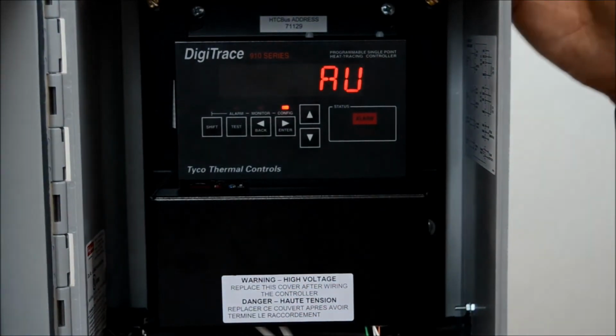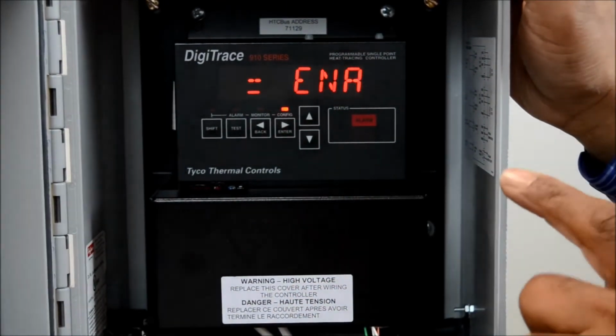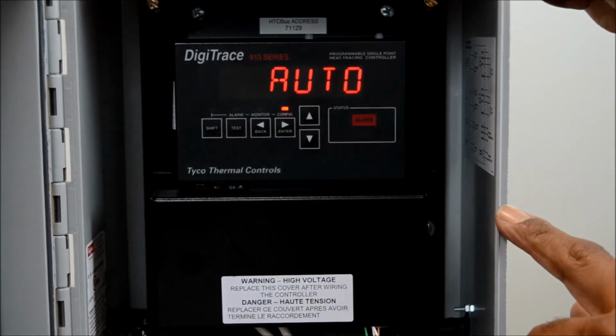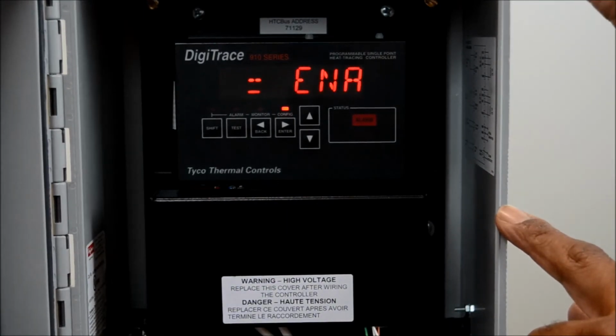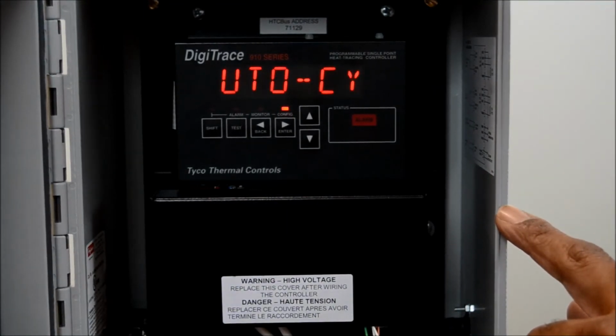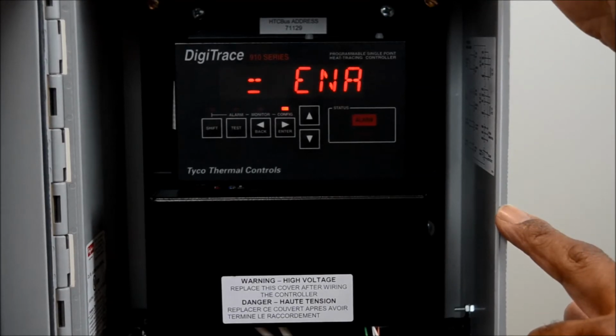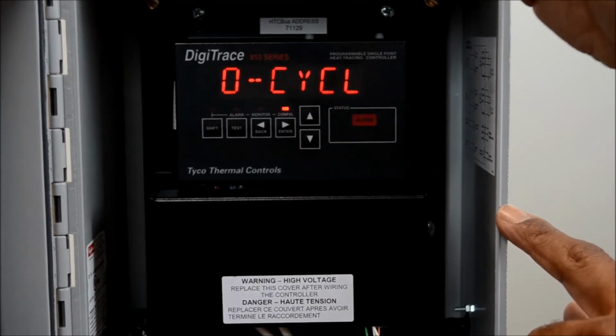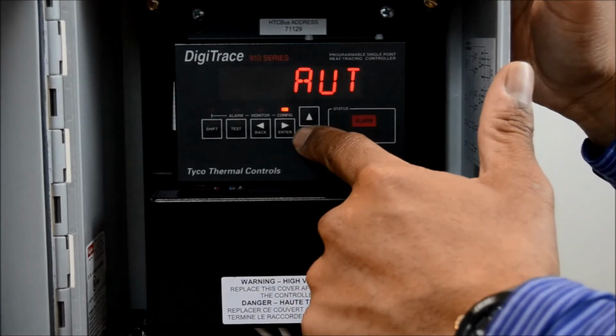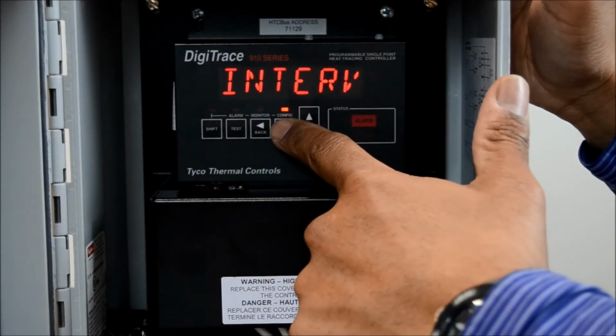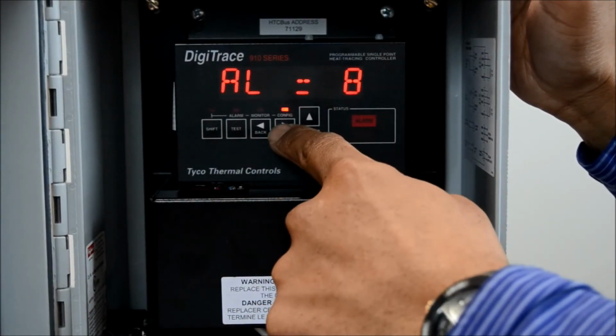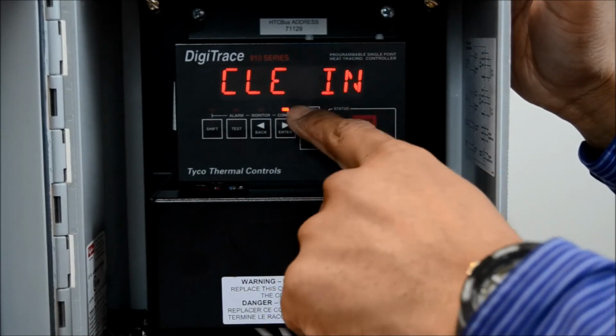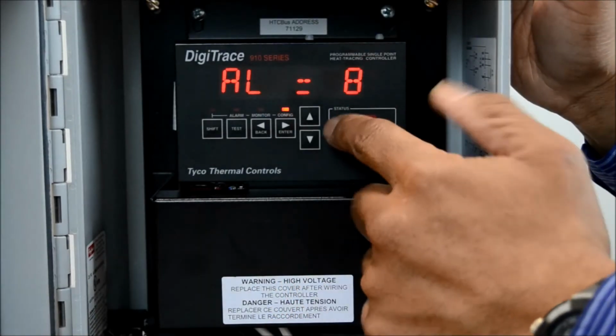Now, one of the other features that this has is an auto cycle. You can set the test either at 8 hours. Every 8 hours, this will test itself to make sure the heat trace is working. Usually what I like to do is set it at 24 hours, and that's what the interval is. You would change it here. Right now it's set at 8, but you could change it to 24.